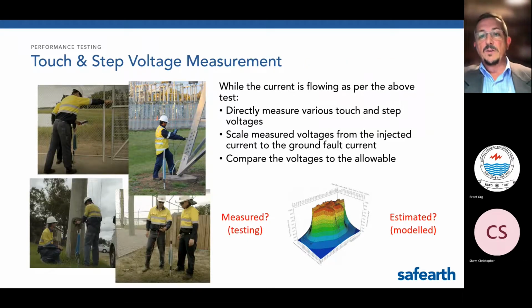These meters can then be used to measure actual touch and step voltages created by the simulated fault. This is a very direct measurement, needing scaling only for fault magnitude and perhaps a small frequency correction. Measurements can be dramatically more accurate than simple calculations and even more accurate than numerical modelling.